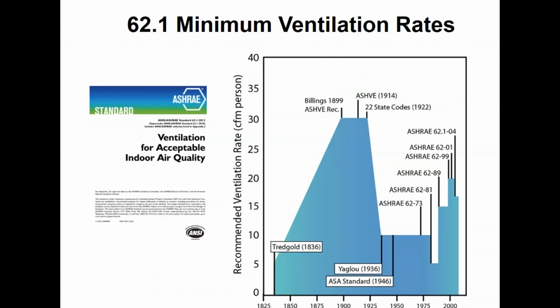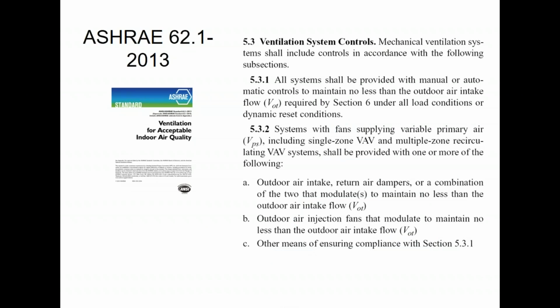All right, other codes that come into play with the control systems. ASHRAE 62.1, which is the IAQ standard, is very closely associated with the International Mechanical Code. For today's purposes, in this discussion, we can talk about them interchangeably. From these perspectives, both require how much outside air we must bring in by code. And this does relate to our control systems. So from a controls perspective, this is what the language would state. You have to have controls that manually or automatically maintain the outside air intake to the prescribed levels, which I'll show you here in a second. Systems with supply fans that are variable speed, either single zone VAV, which is staged air volume, or multiple zone VAV, which is a traditional VAV system, shall provide one or more of the following things listed there.